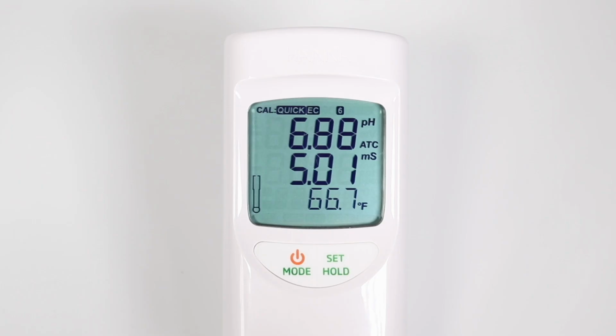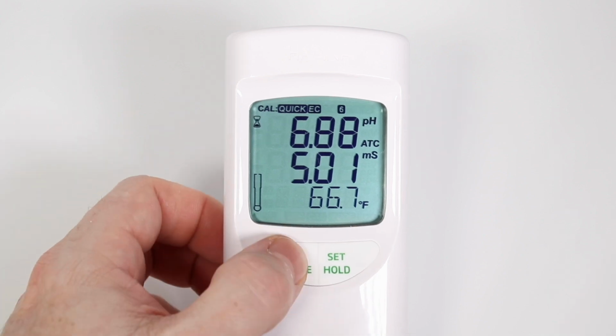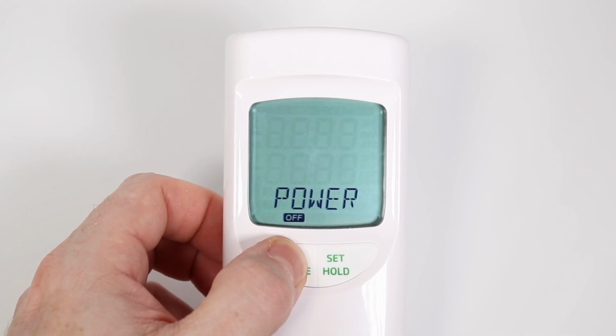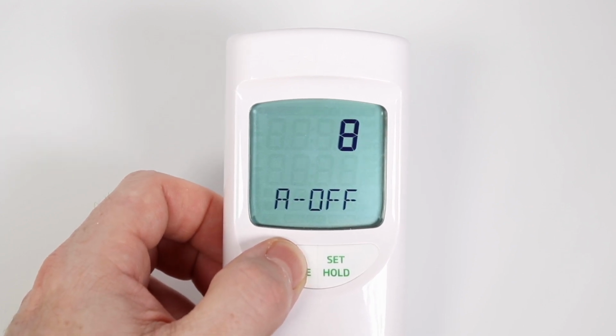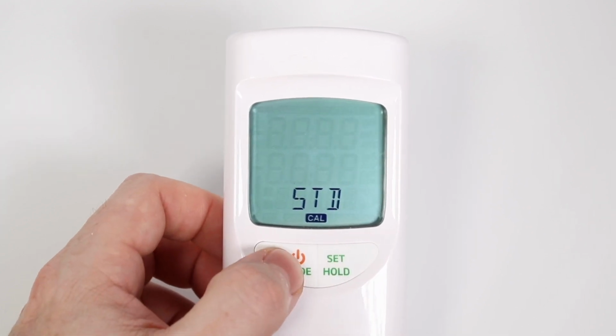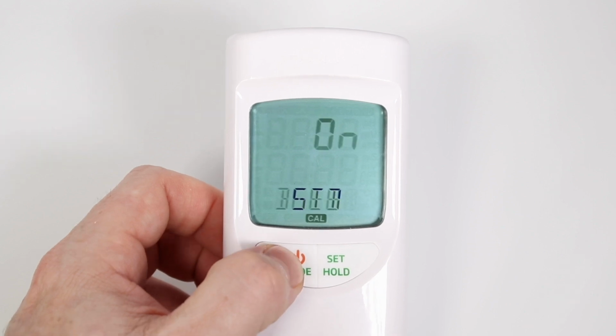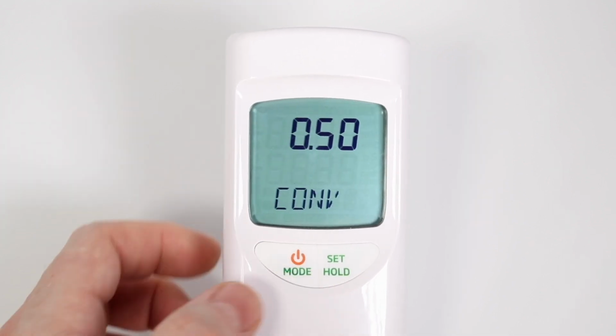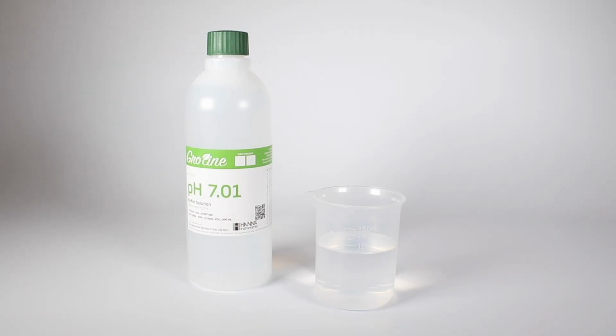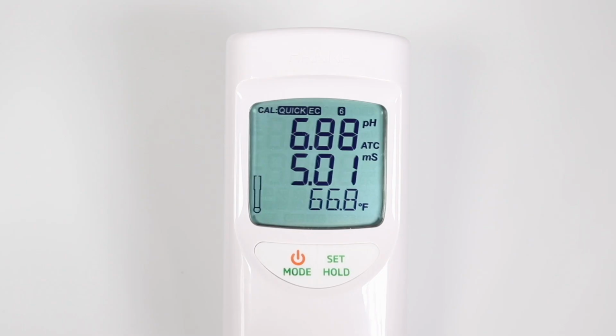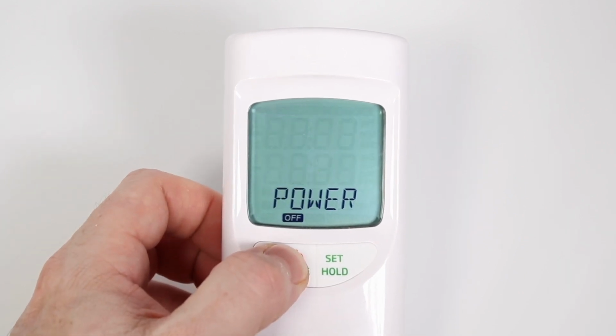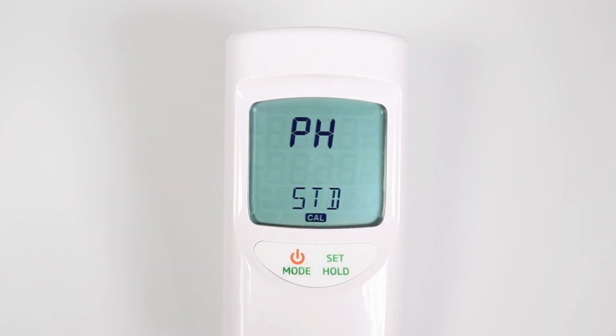To calibrate your meter using Hanna or any brand of 4 and 7 calibration solutions, you must first enter the options menu and switch to Cal Standard mode. Press and hold Mode power button until Setup appears on the screen. Press Mode until Quick Cal is displayed. Then press Set to change it to Standard Cal or Standard Calibration mode. Press Mode 4 times to bring back the measurement screen. Place the probe in the 7 buffer. Hold Mode until Cal Standard shows up. Release the button.